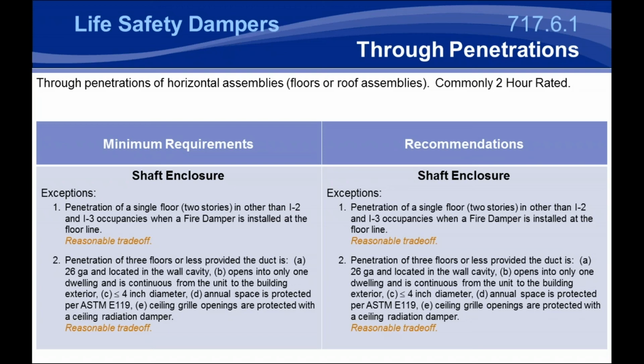So basically anytime you're penetrating more than 2 stories, you're going to need a shaft enclosure, as we talked about earlier. Now, if you're not penetrating more than 2 stories, basically you're going from one story to another, and you can put a fire damper in that floor line, you can remove the shaft requirement. That's perfectly fine, but the only floor assemblies that you can put a horizontal fire damper in are going to be concrete or masonry. Especially the ones that are load bearing.